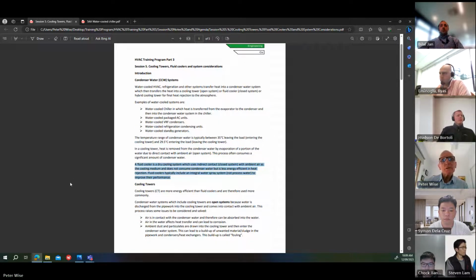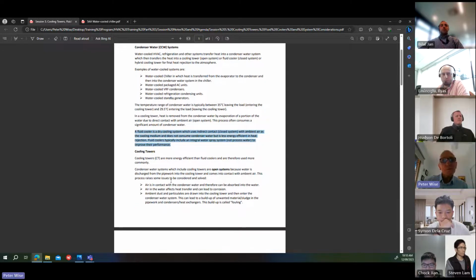In a fluid cooler, it's a dry cooling system and uses indirect contact. So it's a closed system. Indirect contact with ambient air as a cooling medium does not consume condenser water, but is less energy efficient in heat rejection. So the fluid cooler has a tube bundle. The condenser water flows through a tube bundle. Ambient air flows across the tube bundle, similar to an air conditioning unit, if you like. So there's no direct contact of the air and water. It's a dry cooling process. Fluid coolers usually have an integral water spray system, which is not process water, to improve the performance of the fluid cooler in this case.